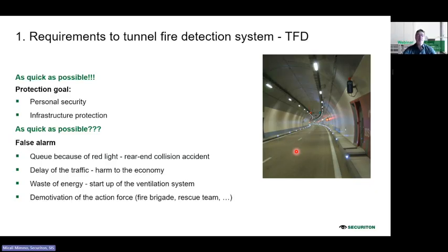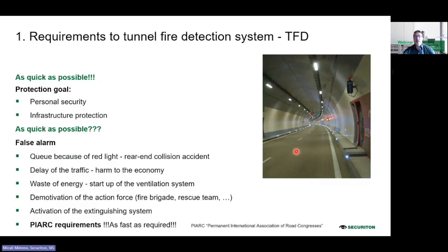And this is also about the motivation, if the fire brigades arrive and see there is no real alarm, it was only a false alarm. So therefore, it's possible to be very fast, but we have to be sure that we don't have any false alarms. Many tunnels today also have an extinguishing system inside the tunnels. They used to have it in different sectors, for example a water curtain, so that the smoke is not passing from one sector to the other. And also here, in case of an alarm, you may trigger an extinguishing system, but it's actually involuntary. So according to PIARC, the Permanent International Association of Road Congresses, it must be as fast as required. Today, I guess 1 or 2 false alarms per year may be tolerated by the operator. More than that, I think it's really critical.